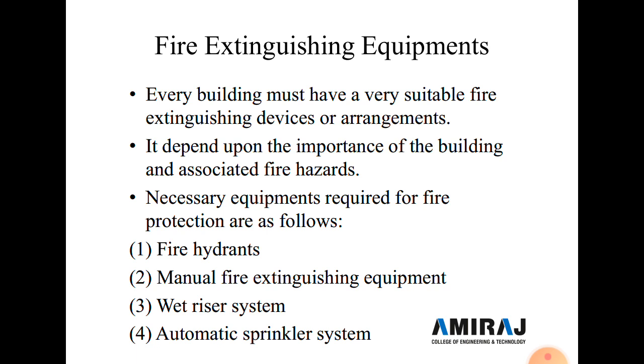Now next we discuss the wet riser system, the third fire protection equipment. The wet riser system is the most effective device, in which vertical GI pipes called risers of 10 to 15 centimeter diameter are provided at suitable locations of the building, and a fire pump is installed to take water from the underground water tank. Here there is much more pressure in the water, so it's easy to control the fire.